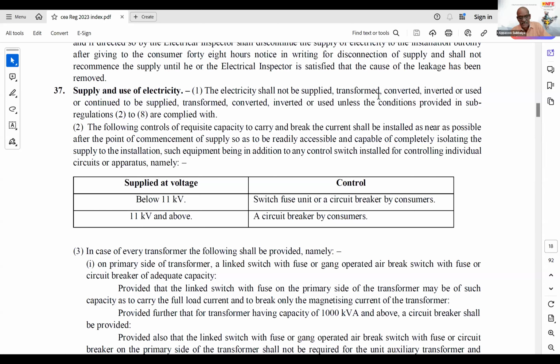Another thing we can say is that it affects the suppliers. I learned from a few consumers that whenever there is a failure of protective gear in the consumer installation, especially these installations, the supplier's equipment gets affected, and they in turn levy a penalty on the consumers. There are cases where, in the protective failure, we can otherwise say the DISCOM is also responsible for the failure of our installation. But here the regulation says that any consumer at 11 kV and above has to provide a circuit breaker. We don't think that it is a wrong concept by the regulator, as well as the cost economy for the consumer. I don't think it will affect the entire project of a consumer.